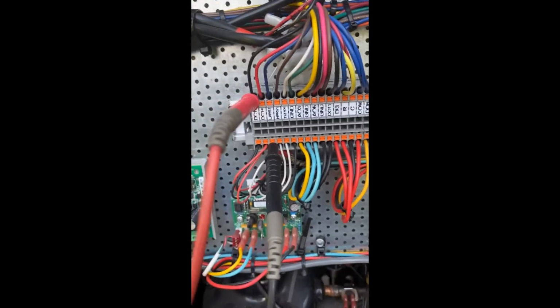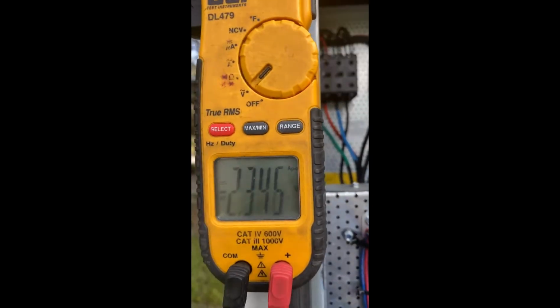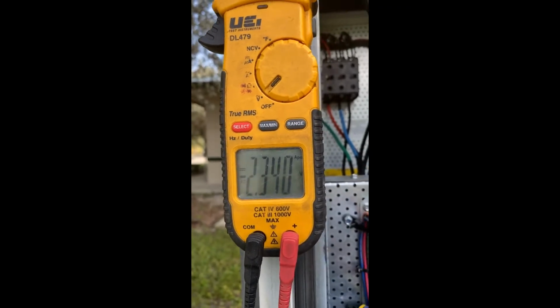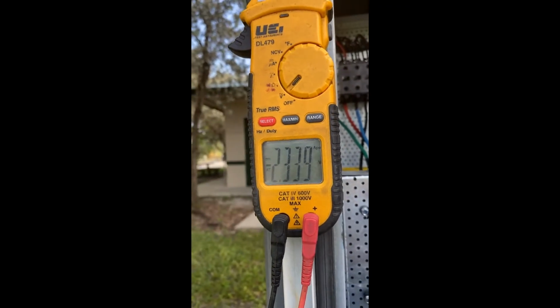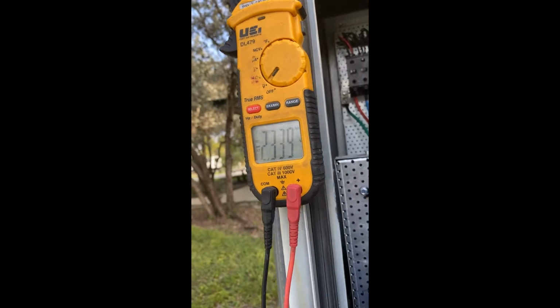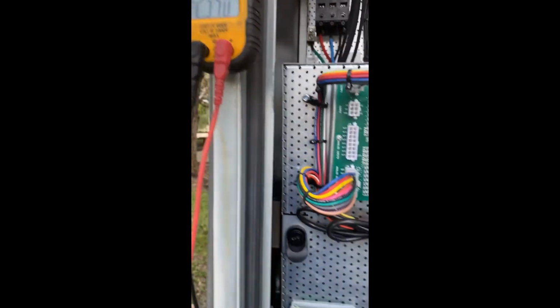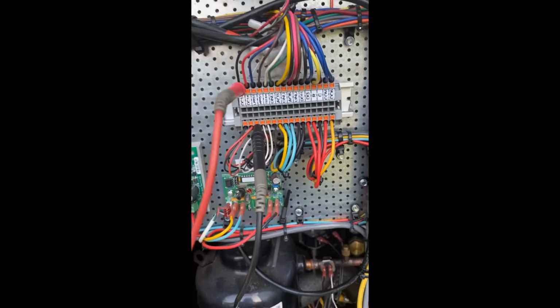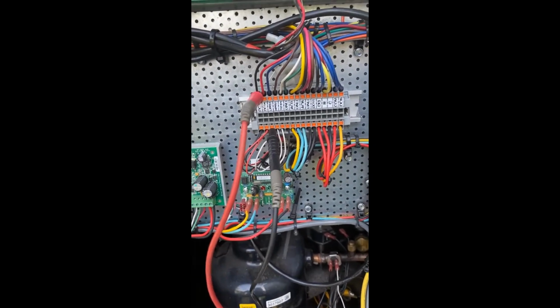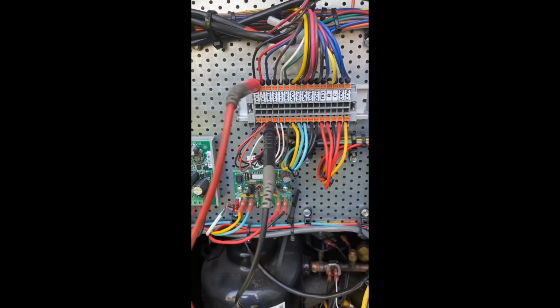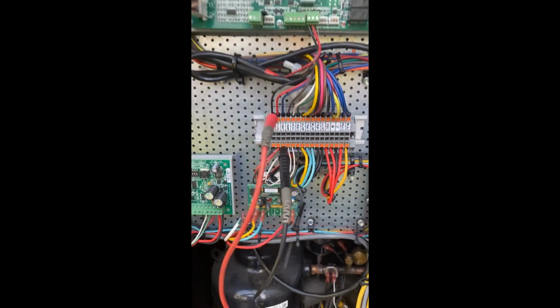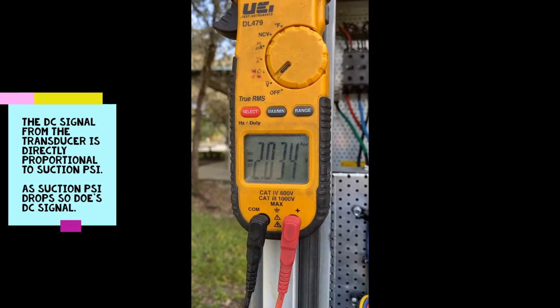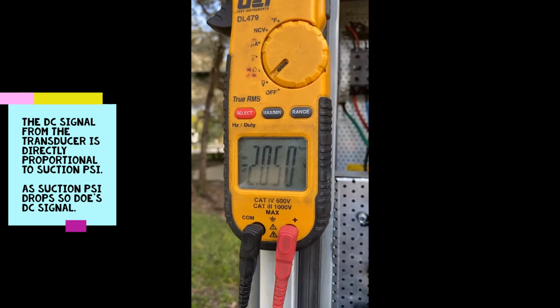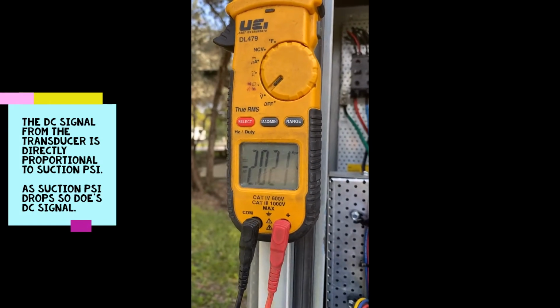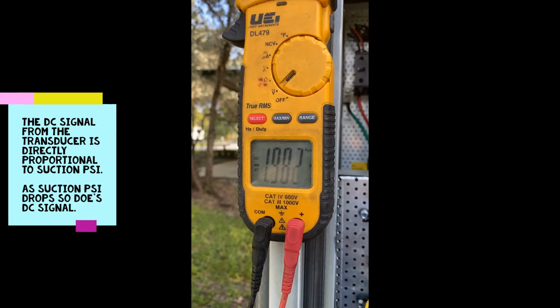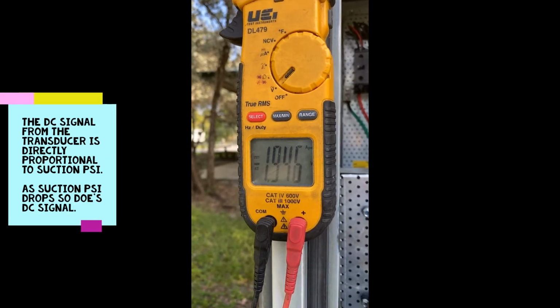So right now, the new transducer I put is giving me 2 volts. Okay, so it's sending out a signal. So that's then after we will be able to see the temperature it's actually reading on the controller. I'll try to show you that afterwards. Good. Right now I just put it on. You'll see it'll start to change because my pressure starts to drop. See it? My suction is dropping, so it's doing what it's supposed to.